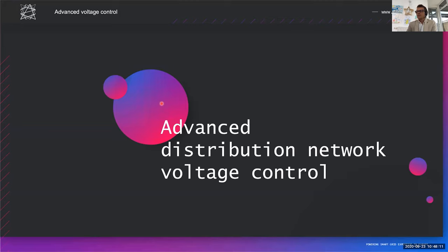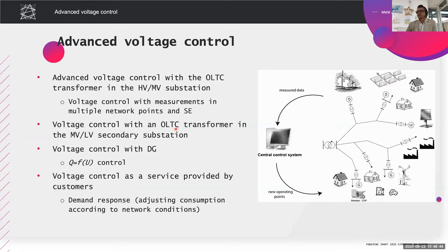So the hosting capacity means the capacity of the network to accommodate renewables or heat pumps or electric vehicles without the requirement to substantially increase the size of the transformers or the cross-section of the power lines, so without the need to excessively reinforce the power network. And of course, that's when the advanced distribution network voltage control comes into play. Here I'm illustrating just some concepts or basic examples of advanced voltage control. One relatively straightforward one is advanced voltage control with the existing tap changing transformer.